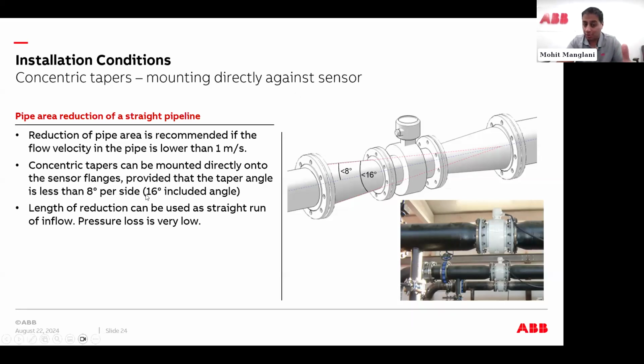Concentric tapers have to be mounted directly onto the flanges. Obviously, you can have rings on the inside of there, and you want to make sure that the taper angle is less than 8 degrees per side. Pressure loss obviously is minimal, and it will be determined by whomever you source your concentric tapers from. So I just wanted to show you what this looked like and what it is.